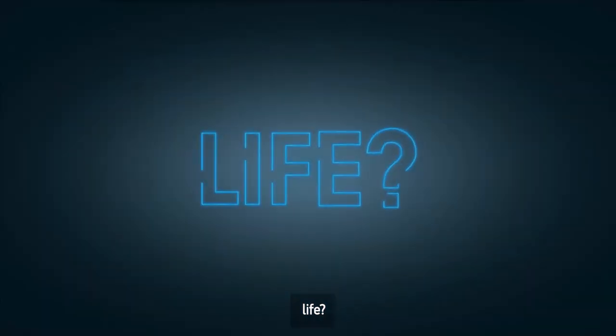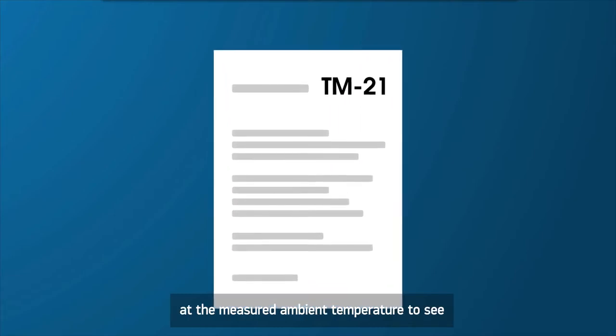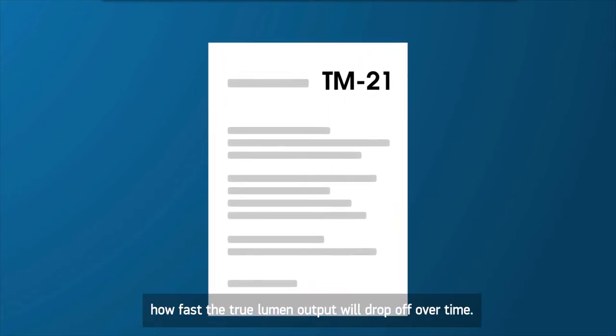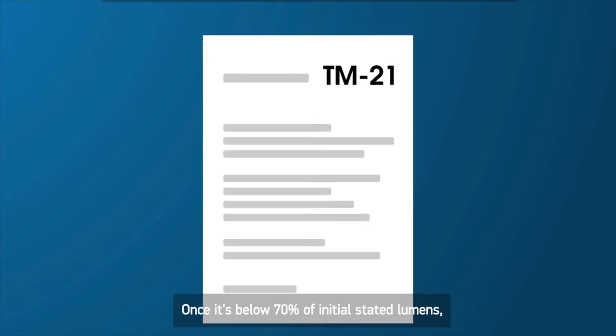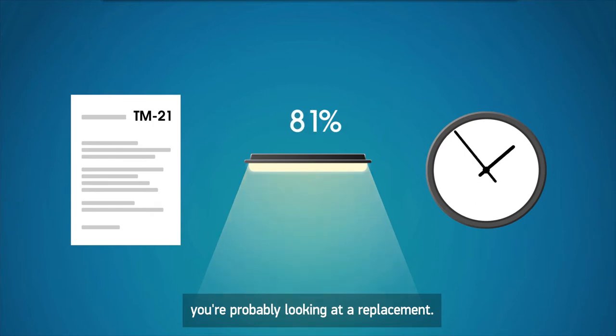And what about life? How long will those lights really last? Ask the manufacturer for TM21 data at the measured ambient temperature to see how fast the true lumen output will drop off over time. Once it's below 70% of initial stated lumens, you're probably looking at a replacement.